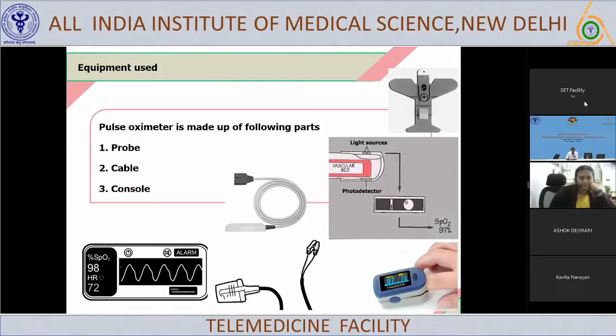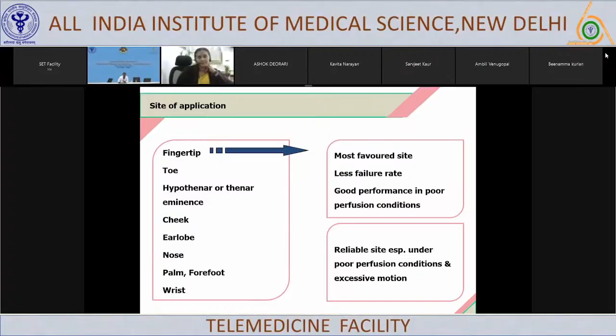Now, which are the sites for application of these types of probes? Usually the most conventional site is the fingertip. You must have seen that the majority of the time it will be on an index finger or a middle finger, because the failure rate is less and the performance is good, even in case of poor perfusion. So try to apply it on a fingertip. But depending upon the size of the probe versus the size of the finger, sometimes if it is not fitting well, it will give an erroneous reading.